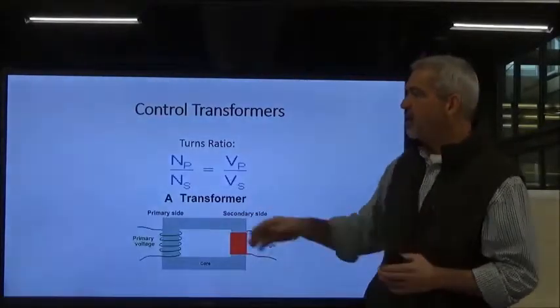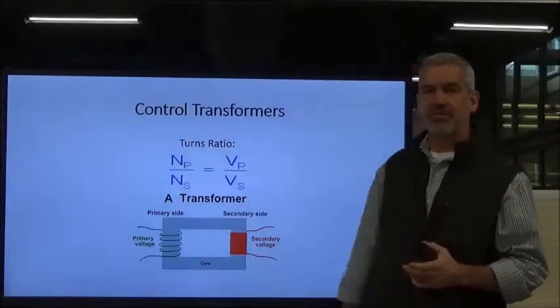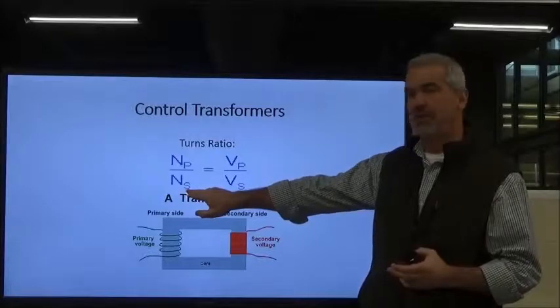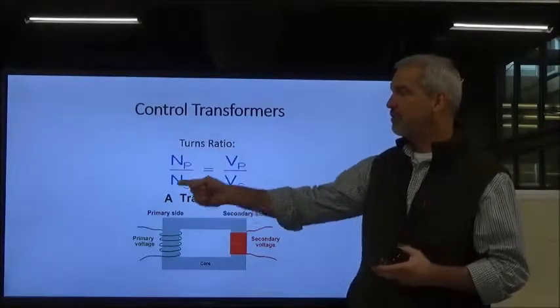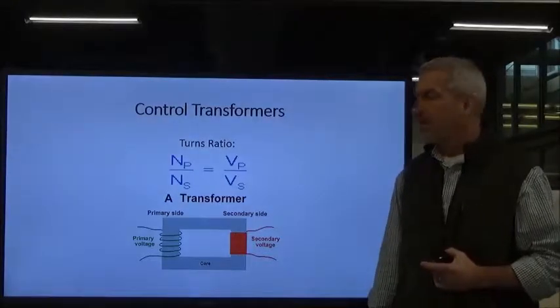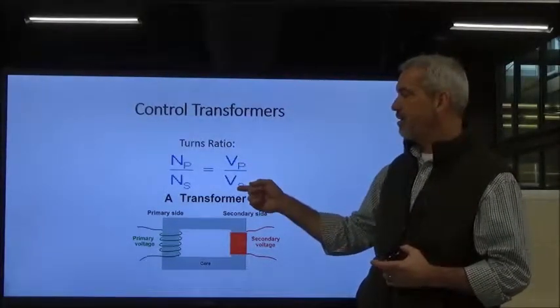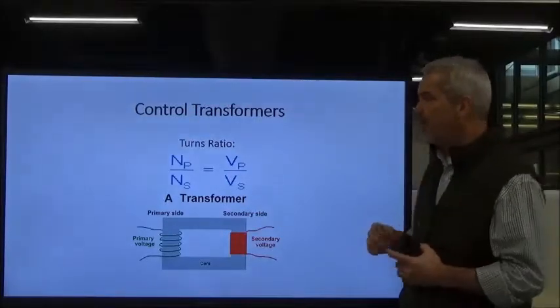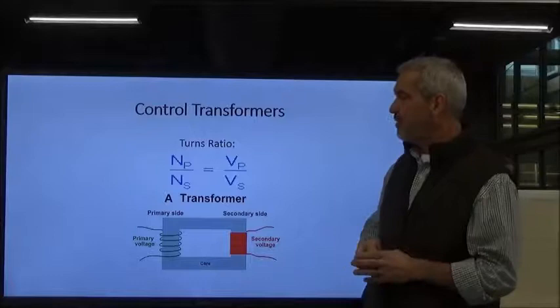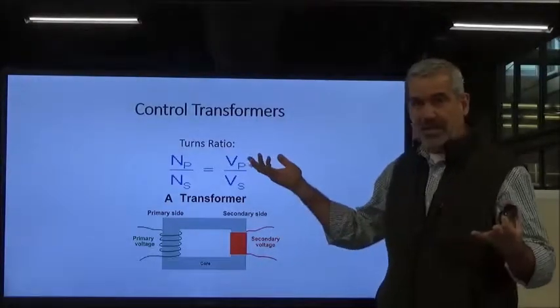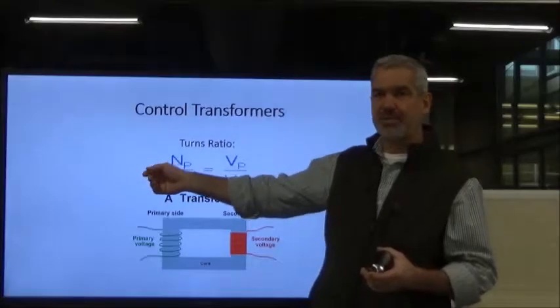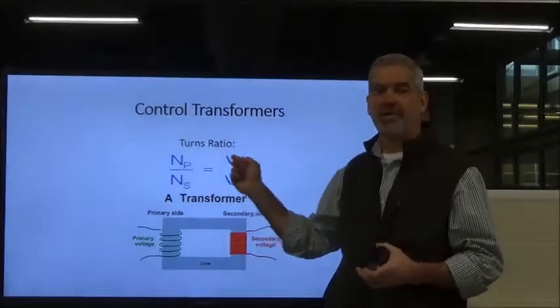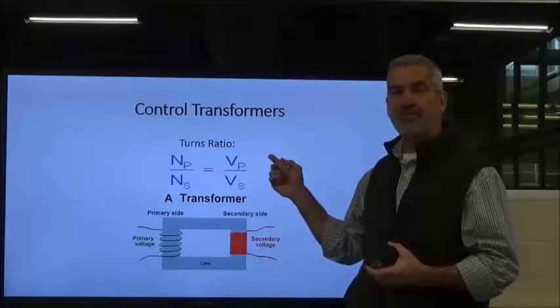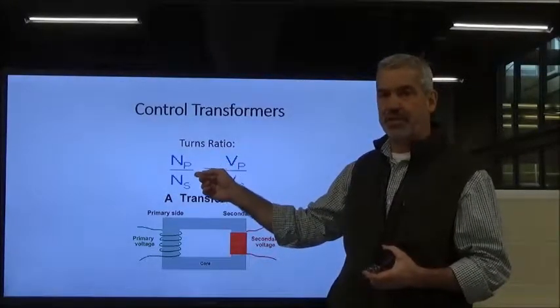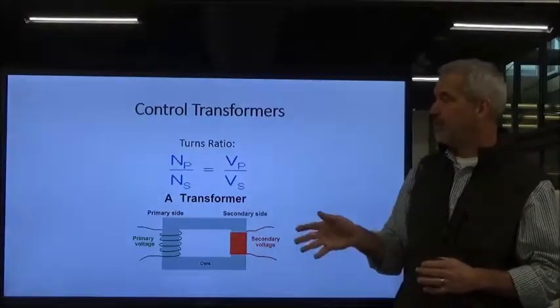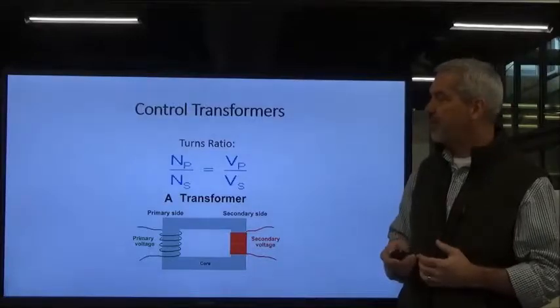So here's how you write it mathematically. N represents the number of turns. The subscript P is for the primary, and the subscript S is for the secondary. So the number of turns on your primary divided by the number of turns on your secondary is the same thing as the voltage on the primary divided by the voltage on the secondary, okay? Also, if you know the voltage on the secondary, say 120 volts, but you don't know the primary voltage, you can turn it around and multiply. With a 4-to-1 ratio, multiply the secondary voltage by the ratio, which is 4, and you wind up with the voltage on the primary, okay? So mathematically, you can figure it all out.